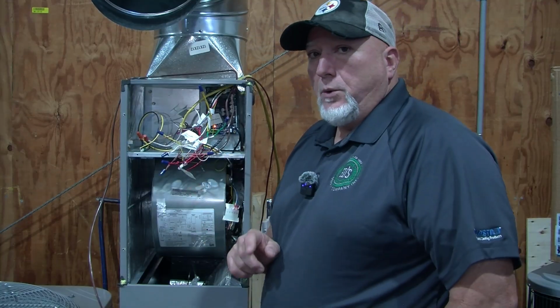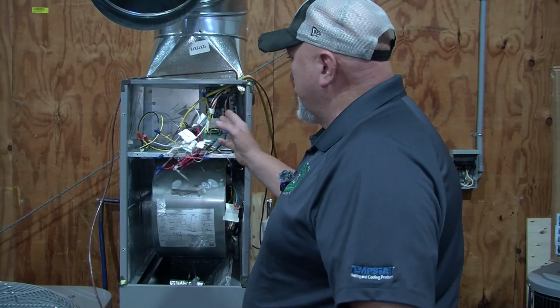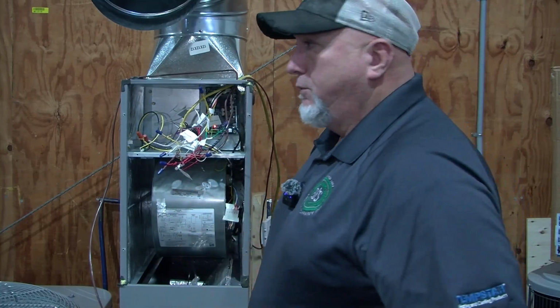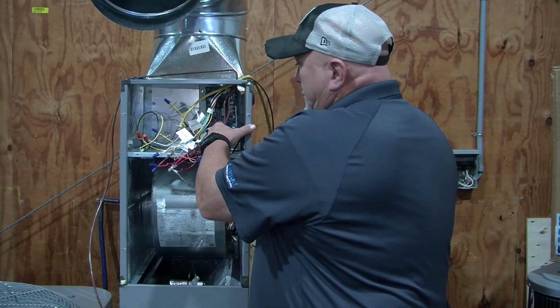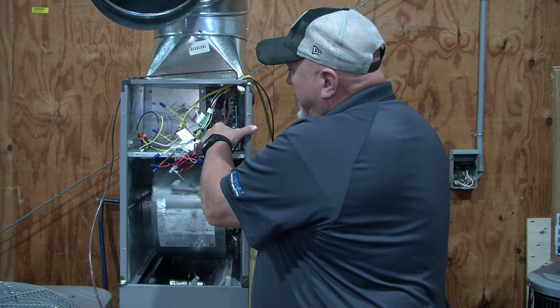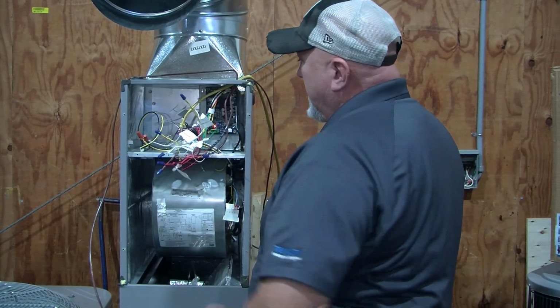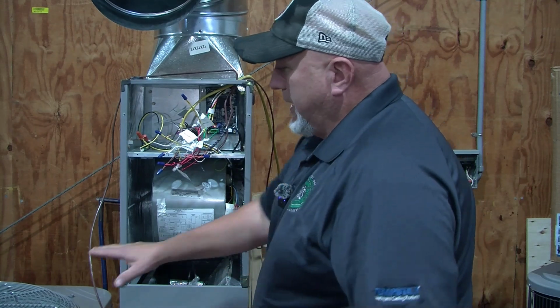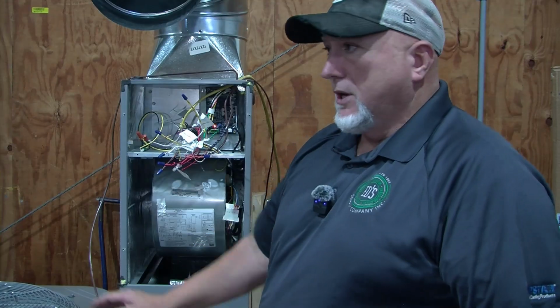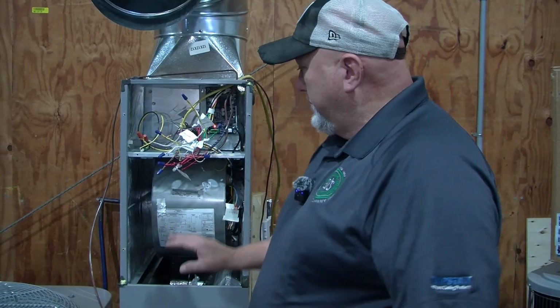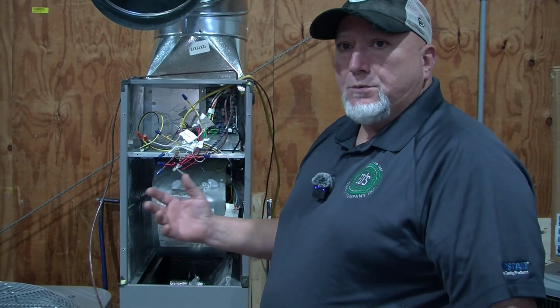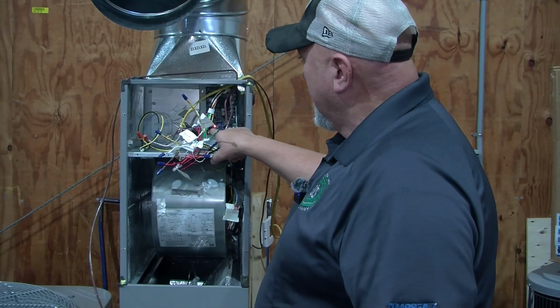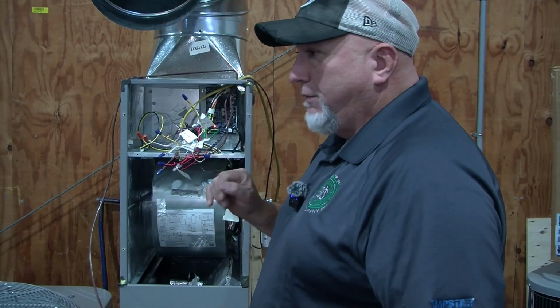Now, here's what I want to do. We're in cool mode, and here's something that every installer should do before they leave the job site: there's a test button. Hold it in 1001, 1002. It's going to go into test mode. It instantly shuts this off, which simulates a leak. And this unit comes off, the blower motor's running, it's dispersing any refrigerant from the leak. You see the flash, that one flash means it is in dissipation mode.